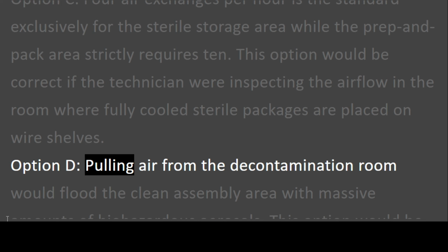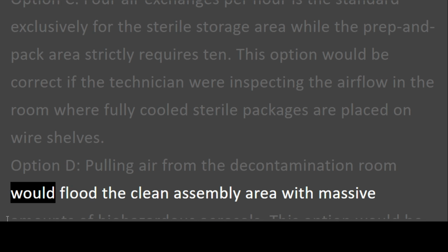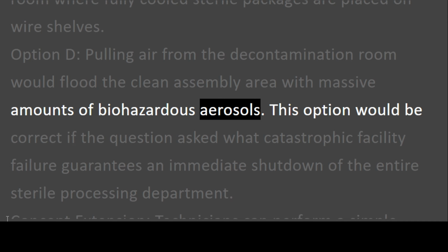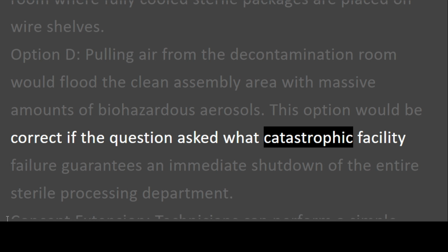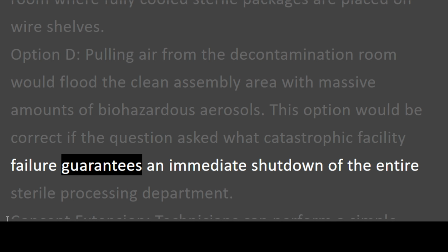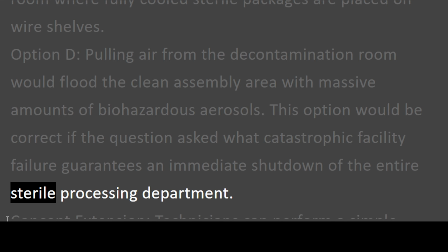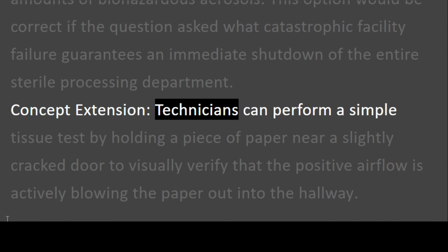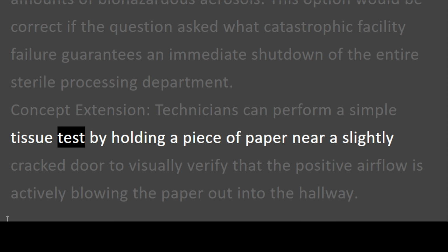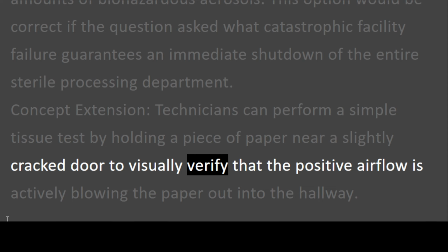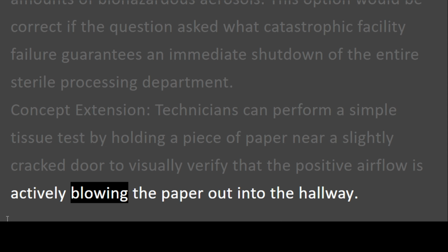Option D. Pulling air from the decontamination room would flood the clean assembly area with massive amounts of biohazardous aerosols. This option would be correct if the question asked what catastrophic facility failure guarantees an immediate shutdown of the entire sterile processing department. Concept extension. Technicians can perform a simple tissue test by holding a piece of paper near a slightly cracked door to visually verify that the positive airflow is actively blowing the paper out into the hallway.